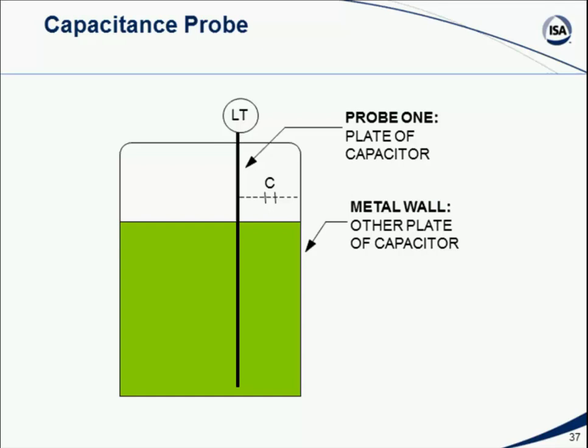And we put a charge across these two plates, and their ability to hold and store a certain amount of electrical energy is directly proportional to what's called the capacitance. So a couple of metal things close to each other, isolated by an insulator, forms a capacitor. So in fact, if I have a metal tank filled, in one case, with a non-conductive fluid, let's say a hydrocarbon, and I can insert down into that tank a metal rod, which of course has to be insulated from touching the tank, then the rod and the body of the tank are two separate metal surfaces, and they form a capacitor.